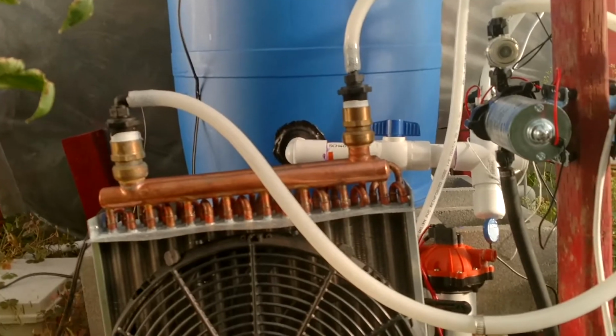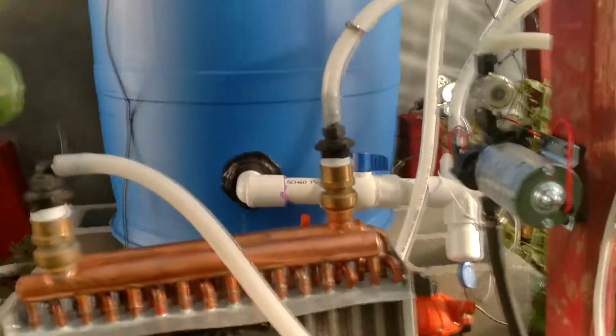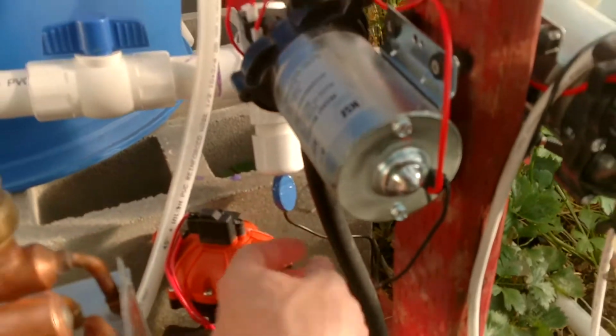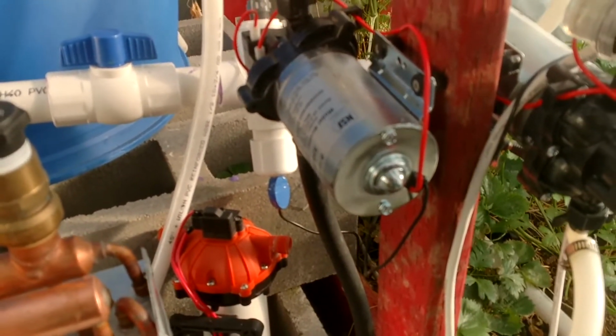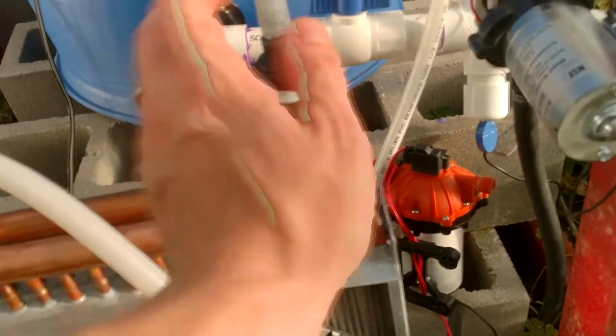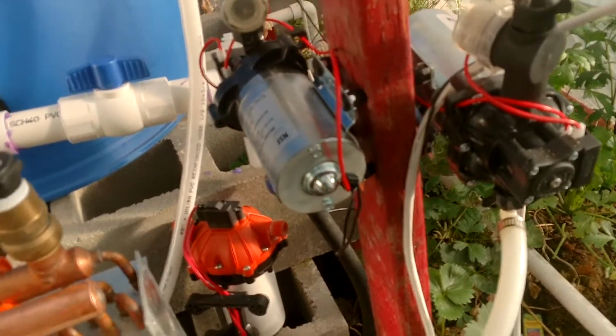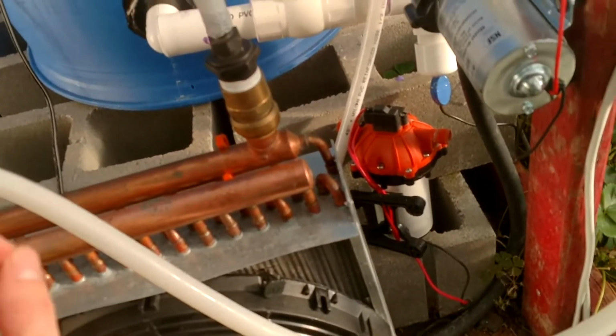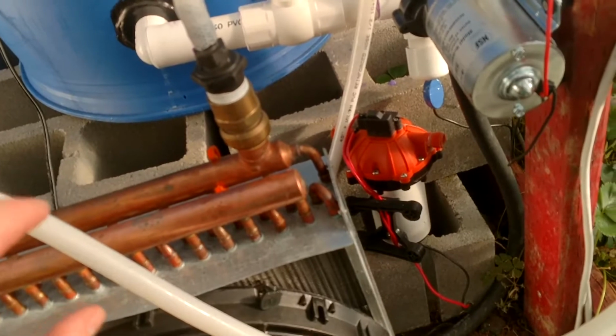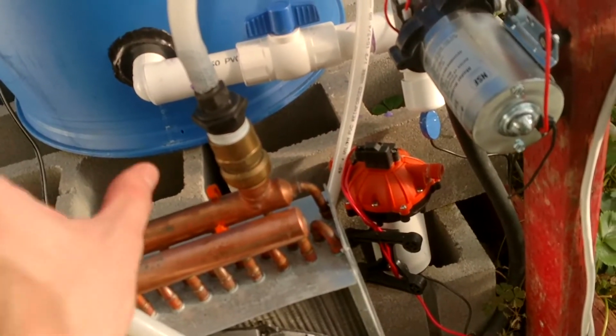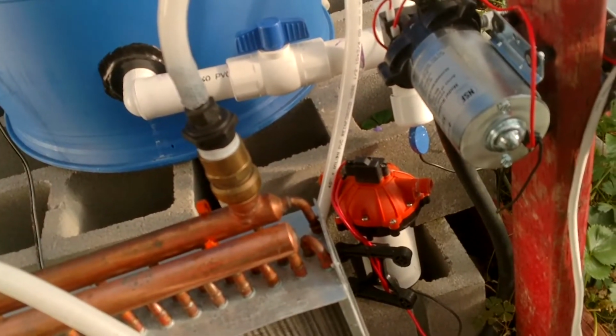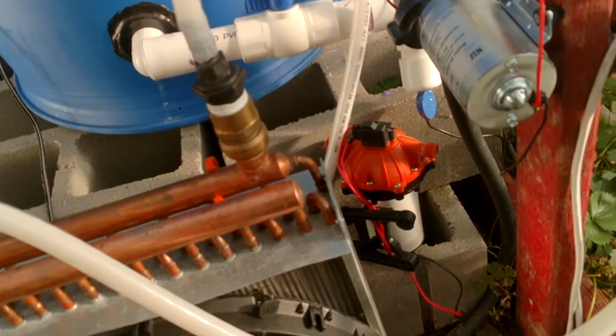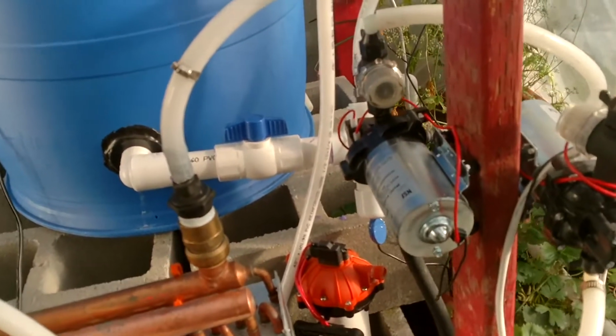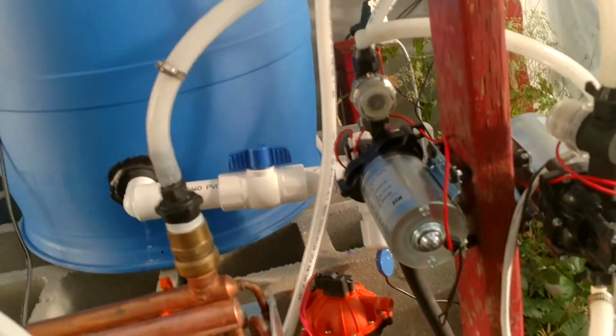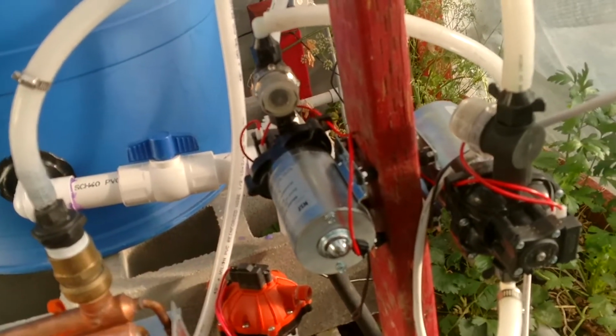If the air temperature is cooler than the reservoir temperature, which I'm reading from this sensor, I use the fan to cool. I keep the pumps and fan going until I get within about 1 degree of equilibrium with the air temperature - the reservoir equals the air temperature plus about 1 degree. Then I shut off the fan and keep both pumps going.